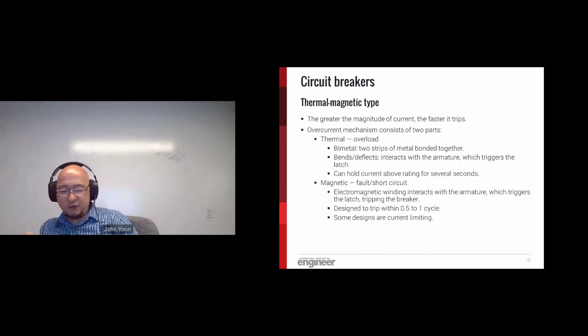Again, we have two distinct conditions that we're trying to protect against, overloads and faults. These two conditions are characterized by the magnitude of unintentional current. There's a big difference between these two. We saw how a dual element fuse addresses these two conditions. But the question is, how does a circuit breaker address those same two conditions? A breaker does this by two distinct mechanisms, a thermal function and a magnetic function.